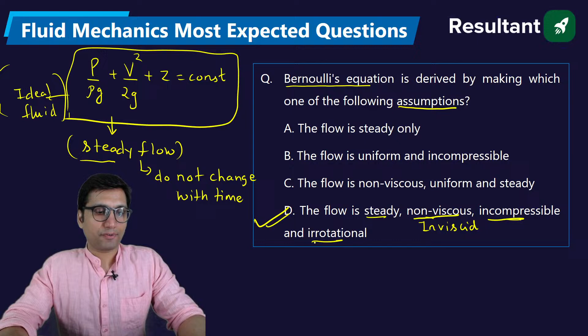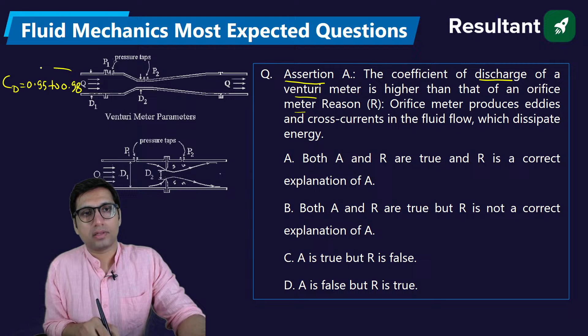Next. Assertion reason type questions can also appear in the exam. You can see the assertion is given as: the coefficient of discharge of a venturi meter is higher than that of an orifice meter. If you know what the coefficient of discharge is, for a venturi meter it is around 0.95 to 0.98, and for an orifice meter it is 0.68 to 0.74.